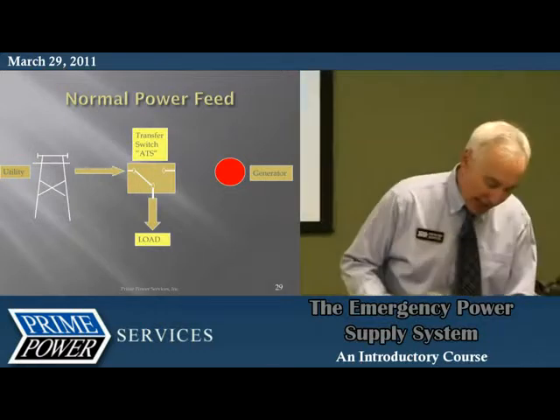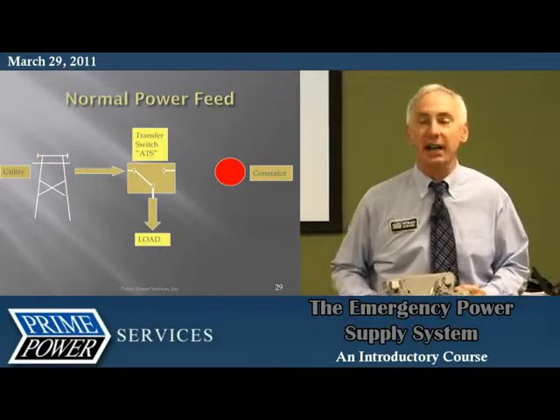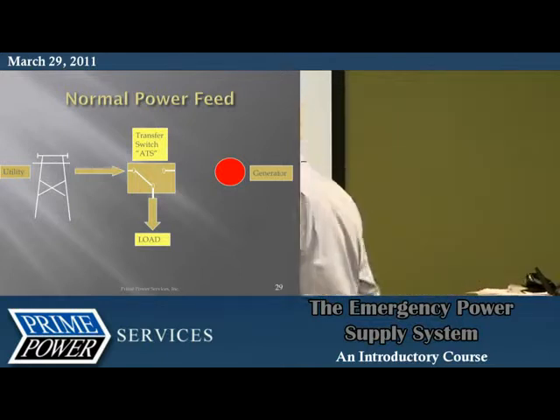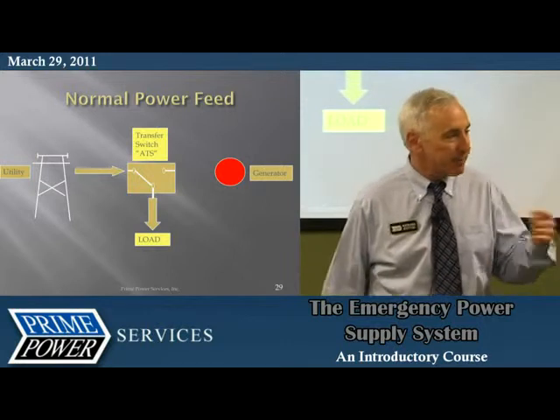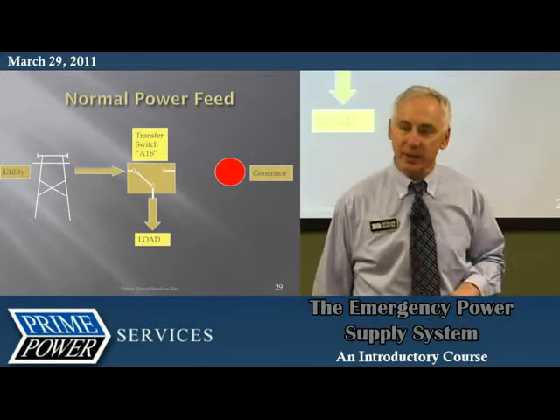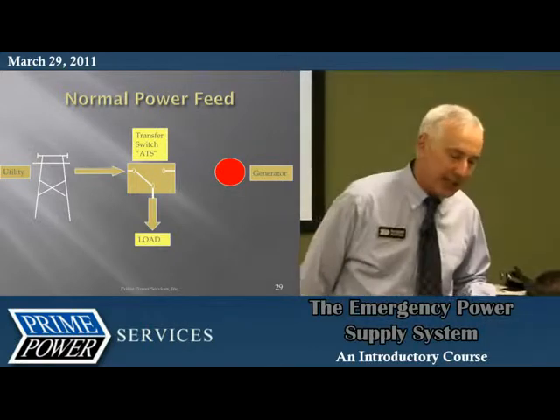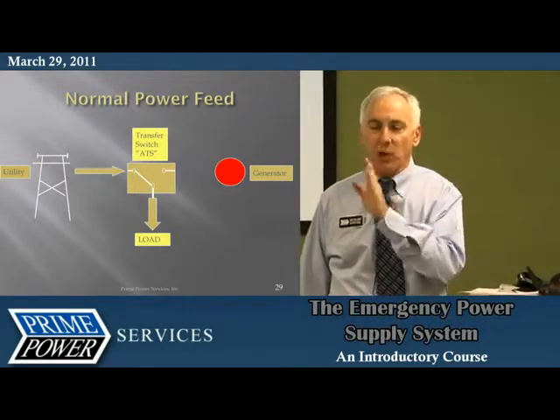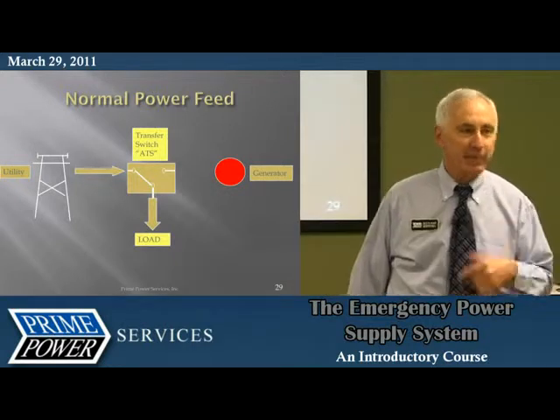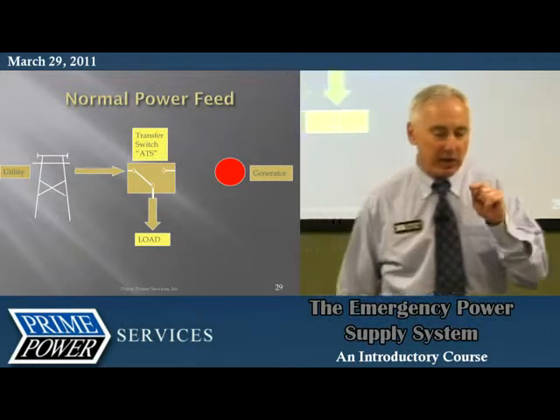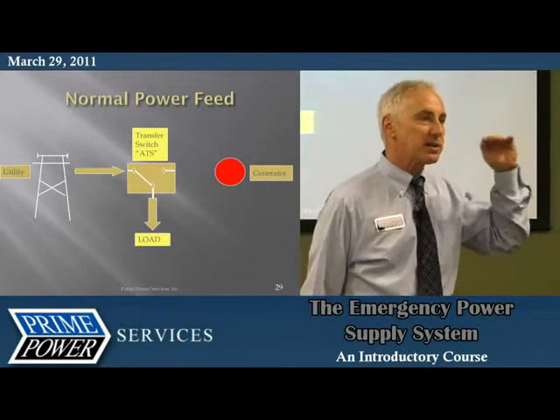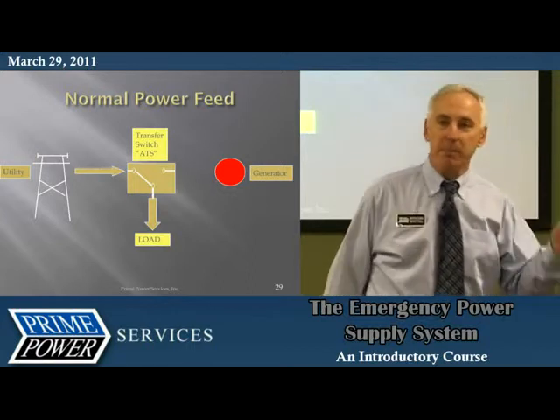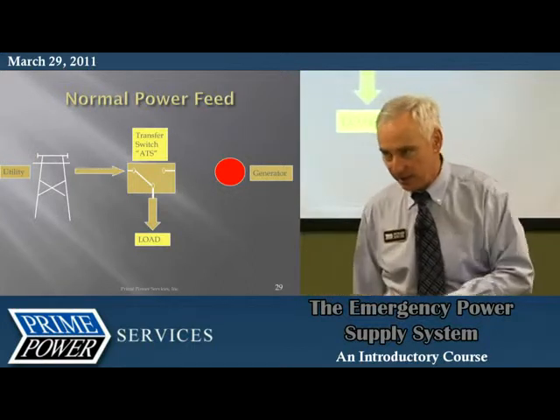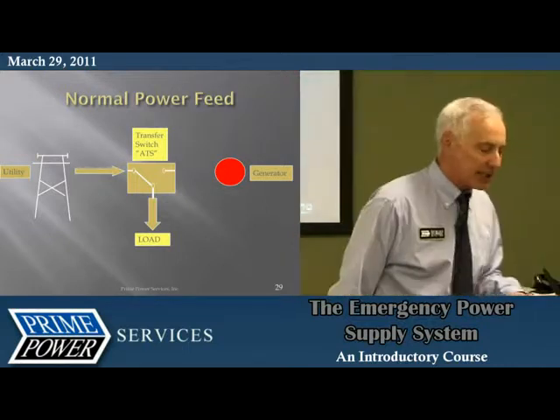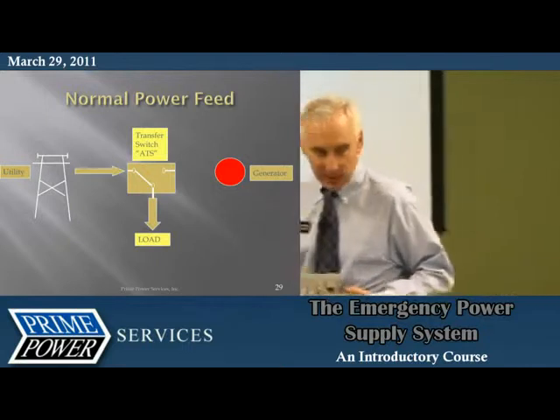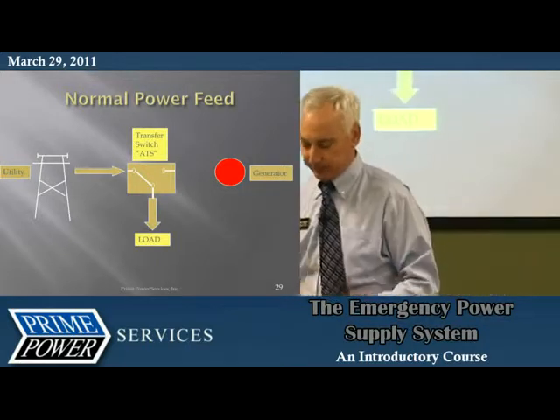But I have no pity for them, I don't really tolerate it very well. Because number one, NFPA 110 says I'm going to test it once a month. A hospital where people can genuinely die tests it once a month, and you're trying to tell me that a data center or facility is so critical we can't test it? Tell me how that makes sense. It doesn't. And if you're at the level where you've informed your superiors of that, my advice is put that in an email - make somebody else tell you that they're not going to allow you to test it. Because if you want a reliable system, the only thing that's going to make it reliable is if you test it. Let me give you my example.